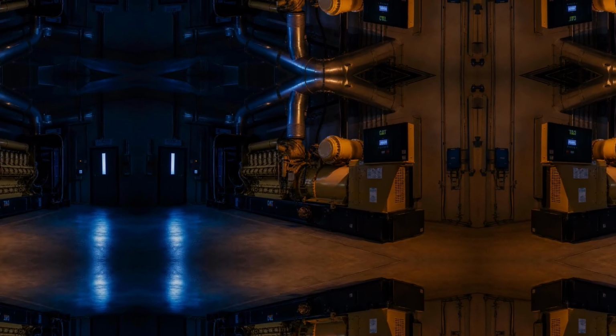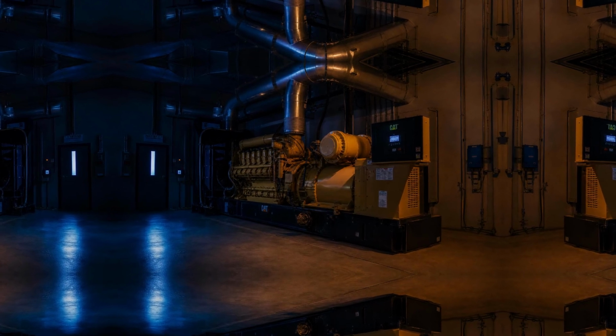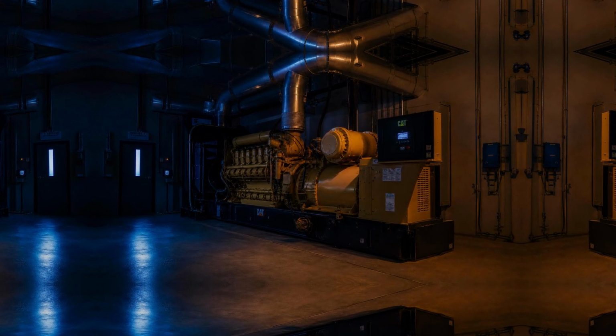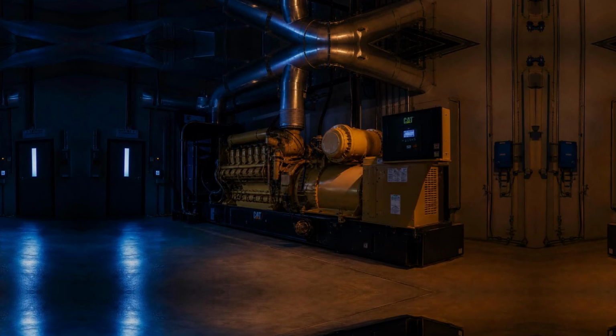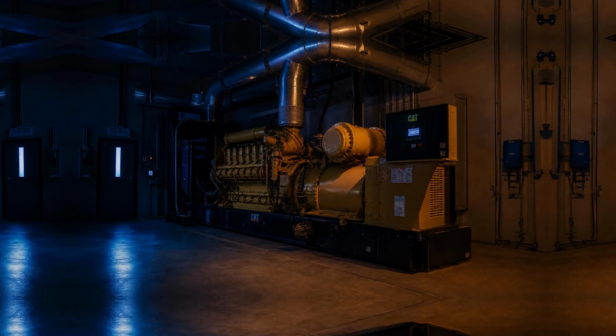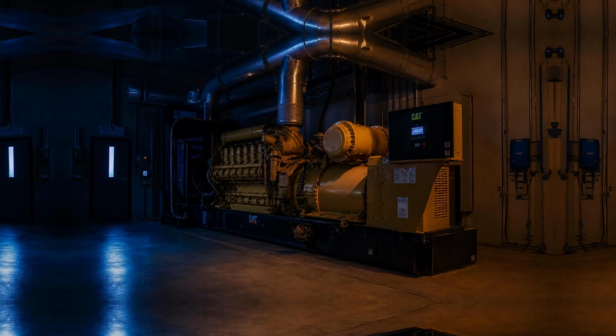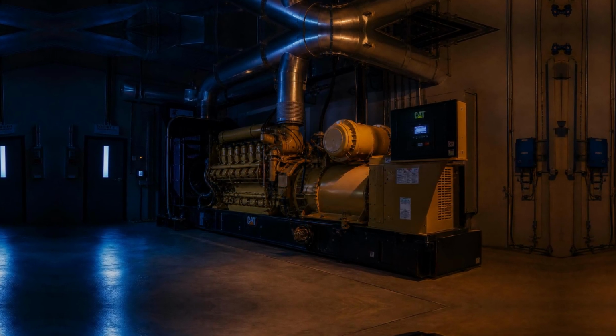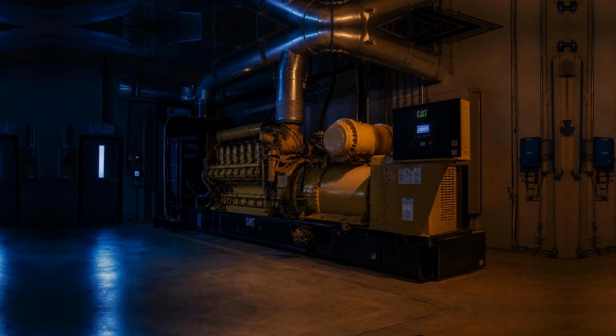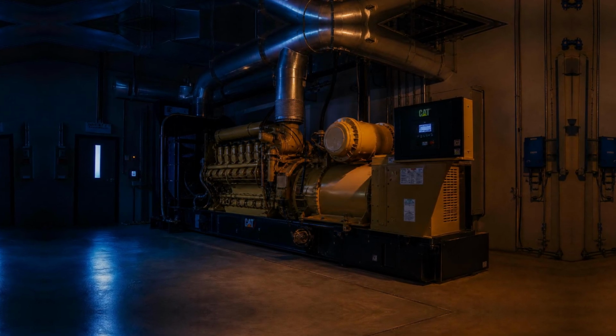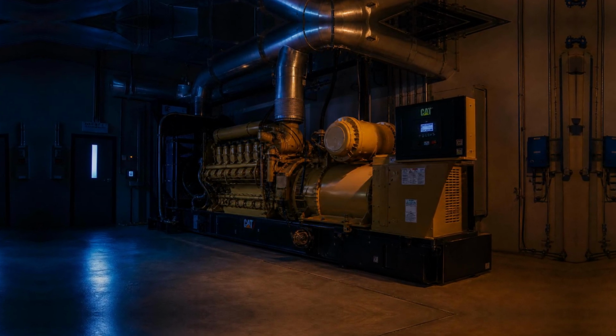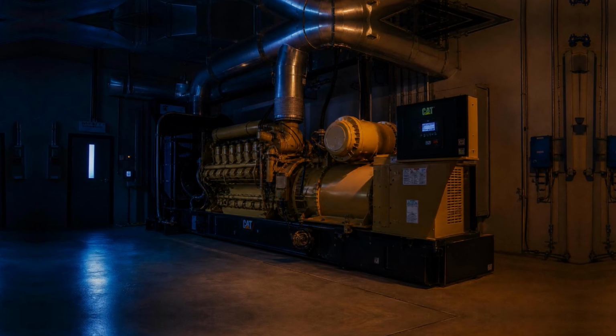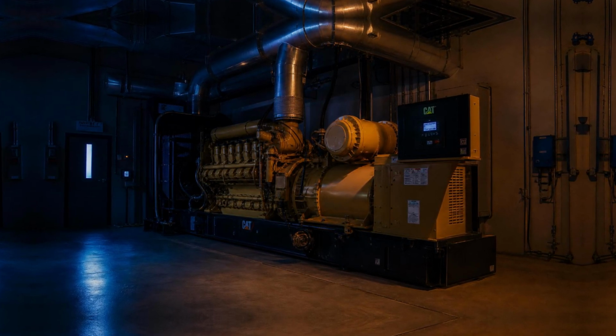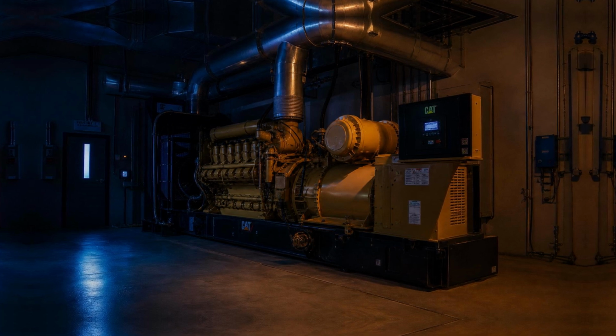The exit signs, which were battery-backed and never went out, are now being supplied by the generator instead of their internal cells. The critical panels are energized. The equipment downstream begins to resume its operation. The building is, in the most important sense, restored, and yet the generator room remains in its state of steady, purposeful activity. The engine continues to run, the alternator continues to turn, the fuel continues to flow from the storage tank through the supply lines to the injection system.